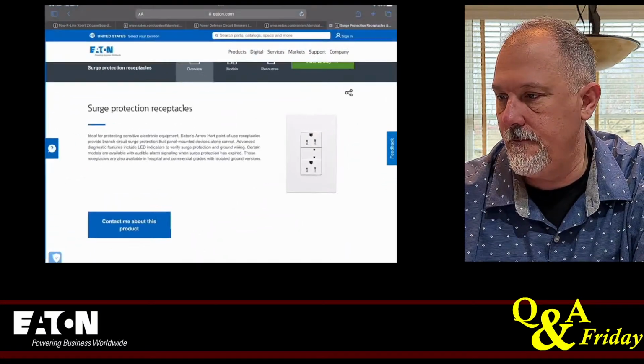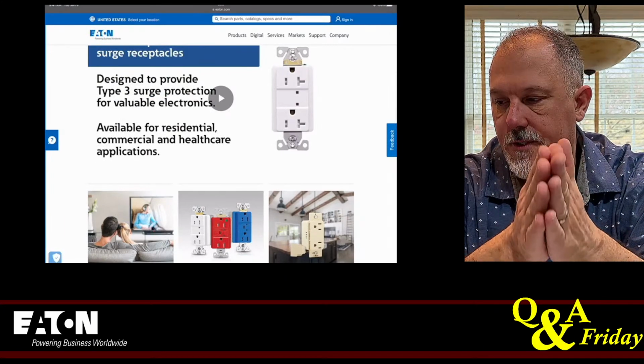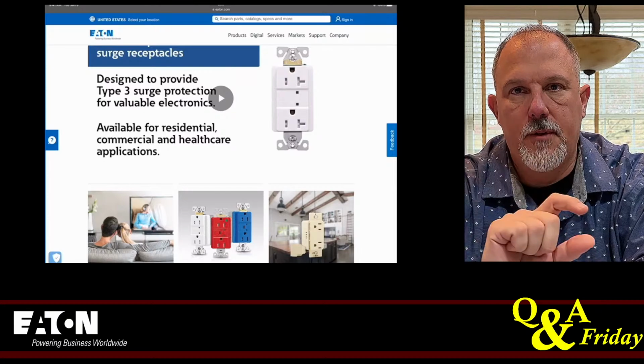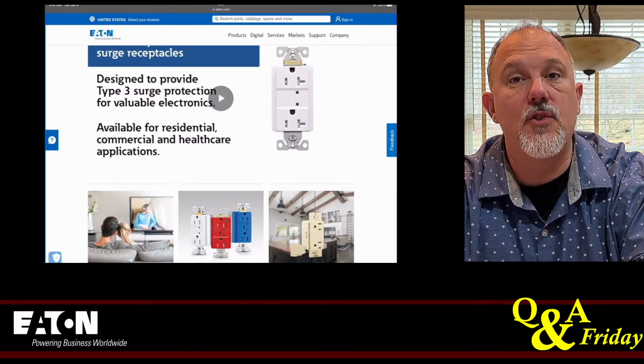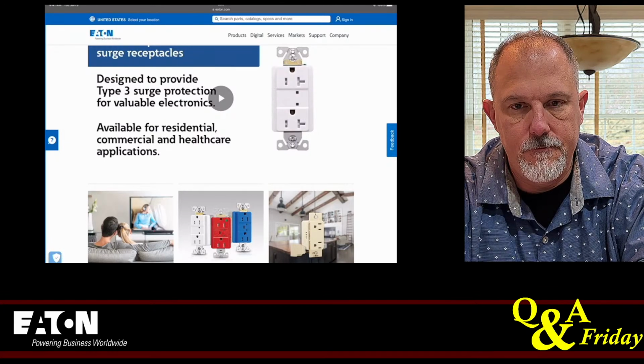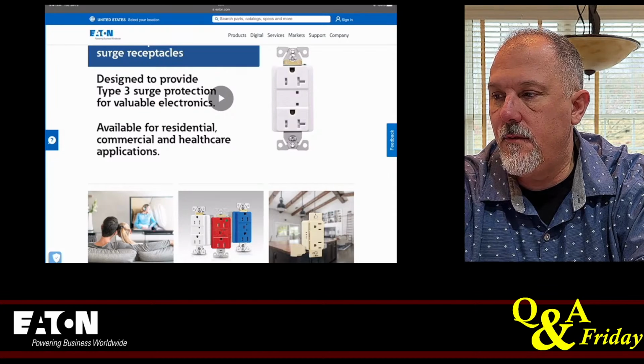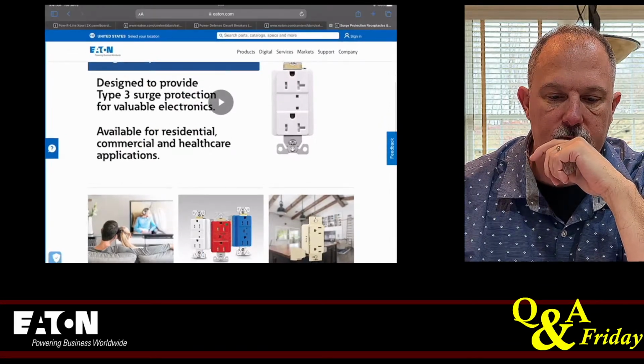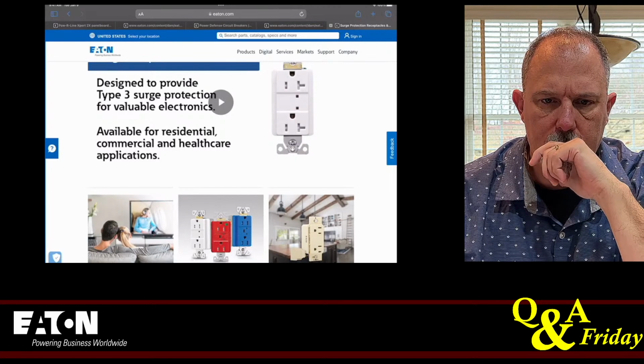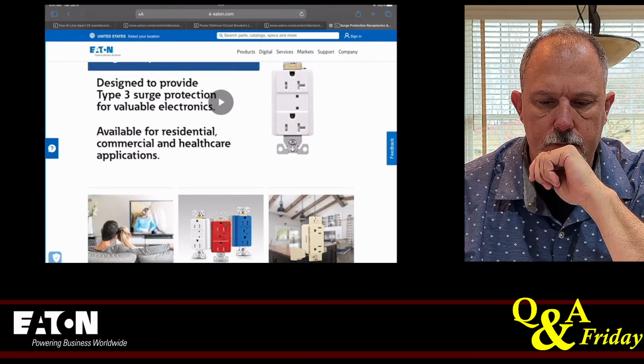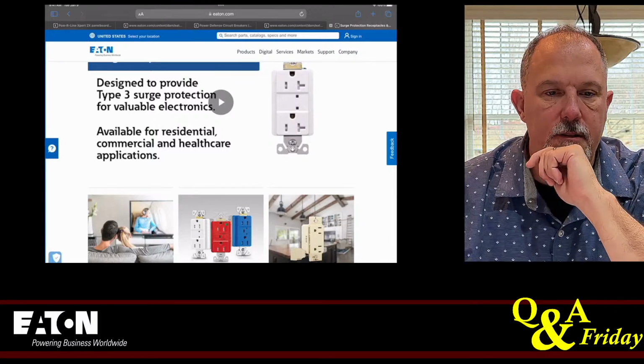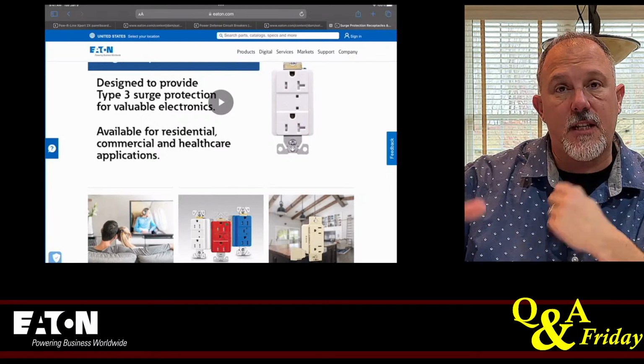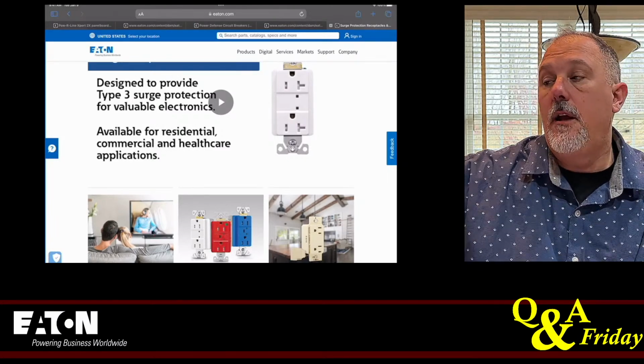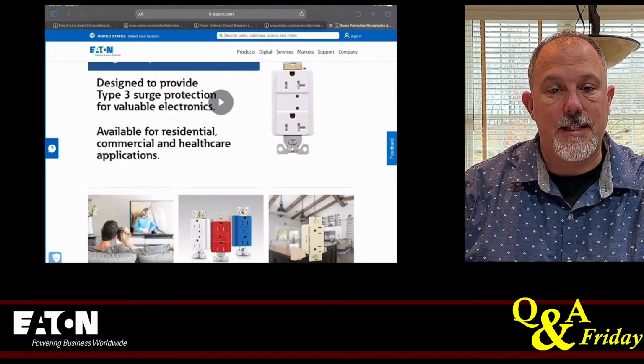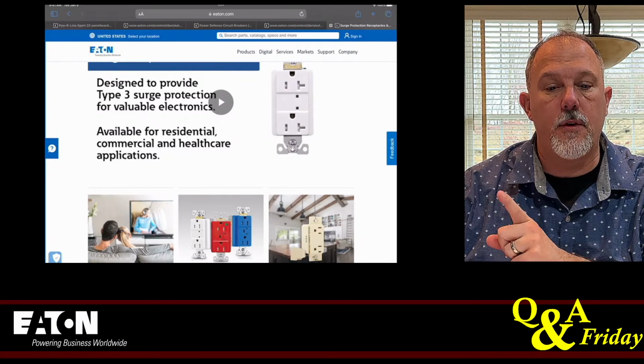Now, here was the question, right? The question was, if I have a 15 amp receptacle with built-in surge protection, can I put it on a 20 amp circuit? Now, these receptacles are listed to two different standards. One is UL 1449 for surges, and the other is 498. So the receptacle itself is listed to UL 498. The surge protected device, the surge that's in that receptacle, is listed to UL 1449.